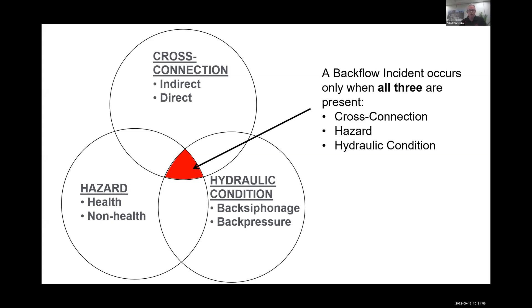Three things have to occur all at the same time: a cross connection, a hazard, and a hydraulic condition. That's when we have an incident — something more serious than just back siphonage occurring. If back siphonage is occurring and air is being sucked in, that indicates there's a hydraulic problem, but that's not an incident in the sense that contaminants or pollutants got into the distribution system.